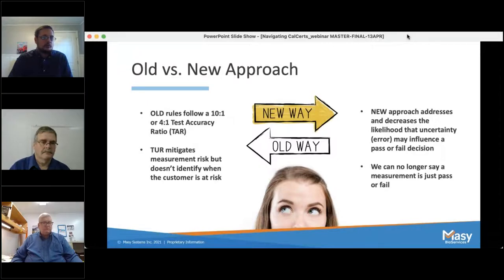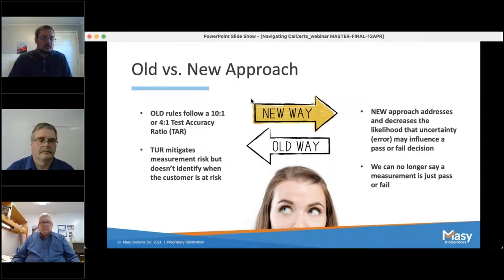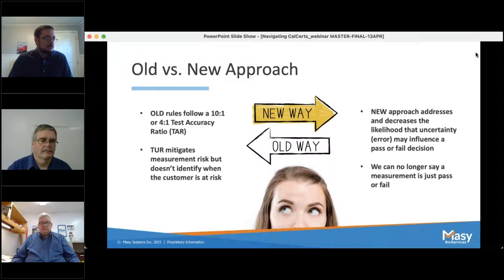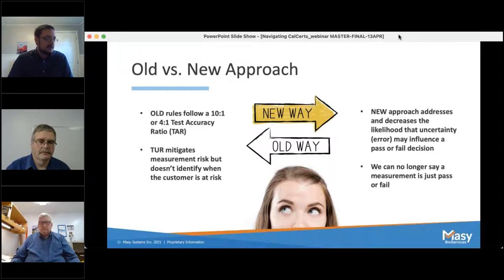So, old versus new approach. The ten to one and four to one TARs have been around for quite a while. They help mitigate risk, but they really don't identify when the customer is at risk. The new approach that Keith was mentioning directly addresses and decreases the likelihood that uncertainty may influence a pass or fail decision. With that, we can no longer say a measurement is just pass or fail — there's going to be a new status that we're going to explain in the coming slides.